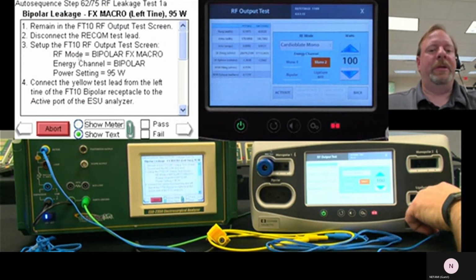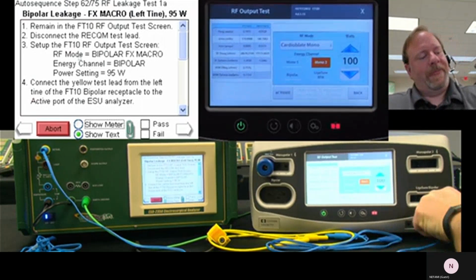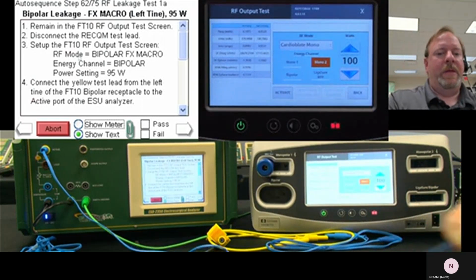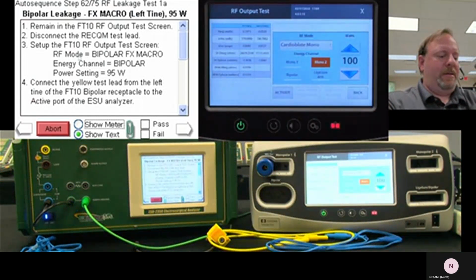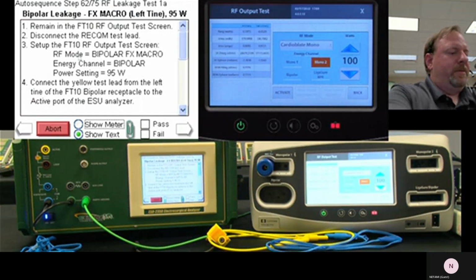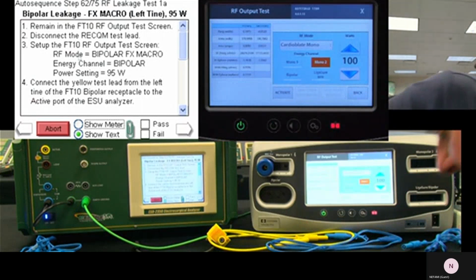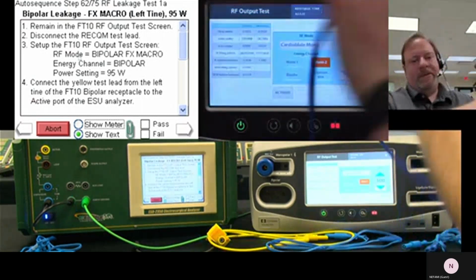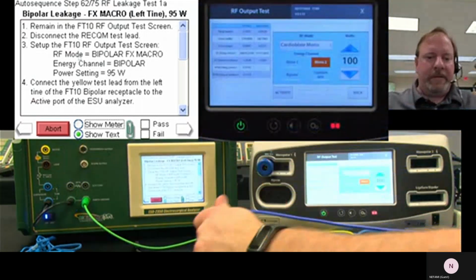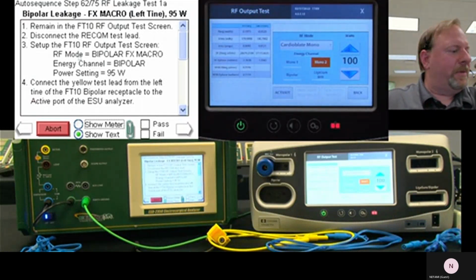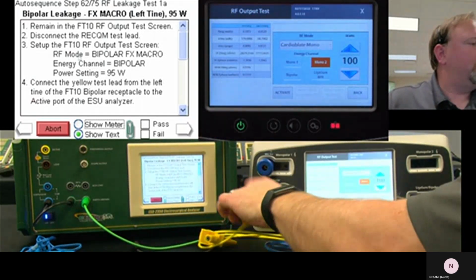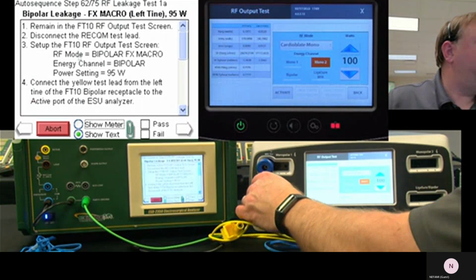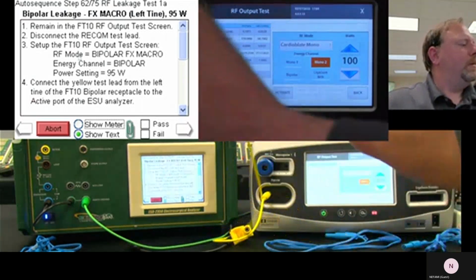Now we're doing bipolar leakage. So remain, disconnect the REM lead. Okay, we can do that. Tangle our wire with an easy reach, and we'll pick up the one I dropped earlier. All right, yellow test lead from the left tine. So one on the left, 2 active.